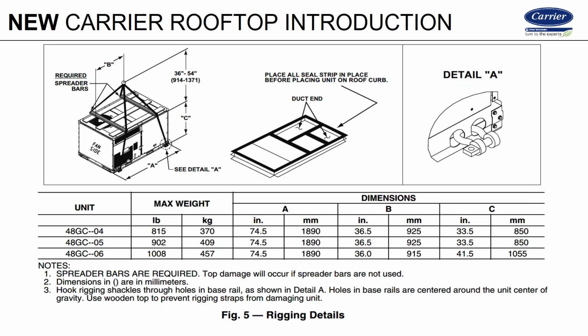The other thing that I see happen, and now let's look at this rooftop. I'm going to call this half right here, and I'm taking it, Brian, you can see the cursor, correct? You've got to move it for me to see it. Right here? Yep, correct. So over here where you have your condenser fan and compressors, I'm going to call this the condenser section of the rooftop. I'm going to call this other half over here our air side. That's going to have our blower, our coil, the return, the supply.